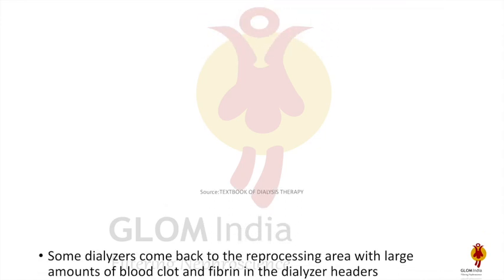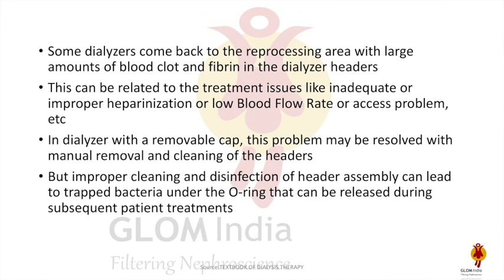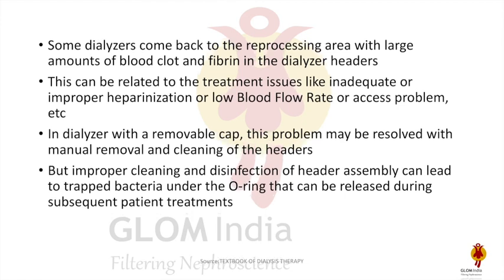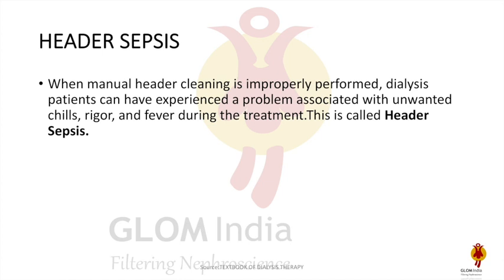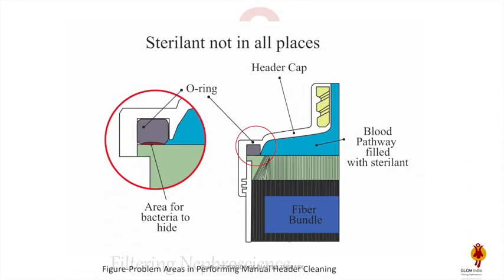Some dialyzers come with openable caps. If a large blood clot is present, we can remove it by opening the header, but if proper procedure is not maintained, this can lead to unwanted chills, rigor, and fever during treatment — this is called header sepsis. The problem is that bacteria can grow in the header area and lead to these reactions. So if you open the cap, it must be placed back in the proper way.